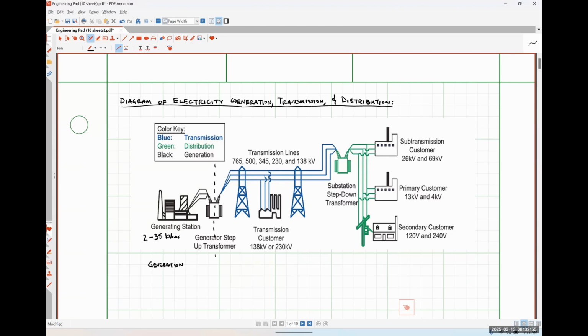So that's essentially exactly right. It has to do with the losses in the system. You've probably heard of copper losses, or I squared R losses—that's your conductors absorbing energy, converting electrical energy into heat as they heat up. Any losses we have are related to the square of the current. So if we can get that current as small as possible, we experience the least amount of losses, meaning we're wasting the least amount of money. So 100% right, it's all about heat management.